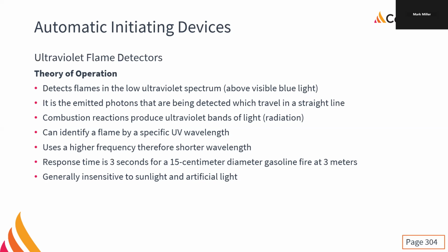Now, testing them. I tried so hard to convince the owners of the hangar to just empty the room and light a bucket of fire in the middle and let it trigger. They wouldn't go for that. I asked, they laughed and said no. So you have to use a UV light source, but it has to be an approved UV light source.